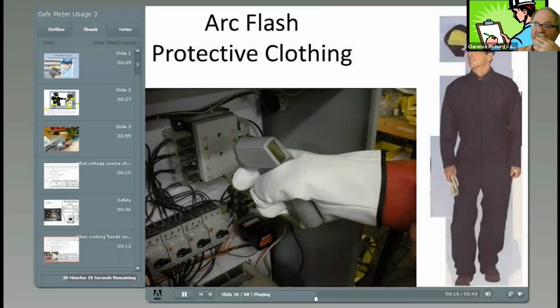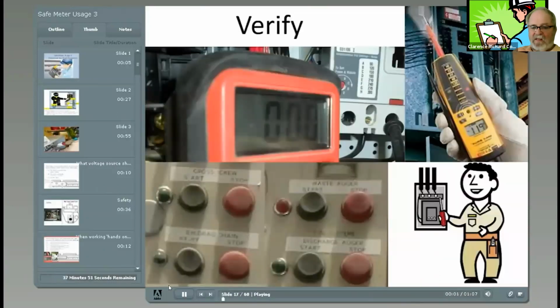Higher voltage circuit. Severe burns can happen when exposing oneself to an open enclosure with higher voltage present. The enclosure must be labeled with warning labels about the arc flash hazard. The operator is using a temperature gun aimed at the terminals to look for excess heat generated when terminals and wires are not making a good connection. The rubber glove inside a goatskin glove not only protects against arc flash, but insulates the troubleshooter from coming in contact with the circuit.